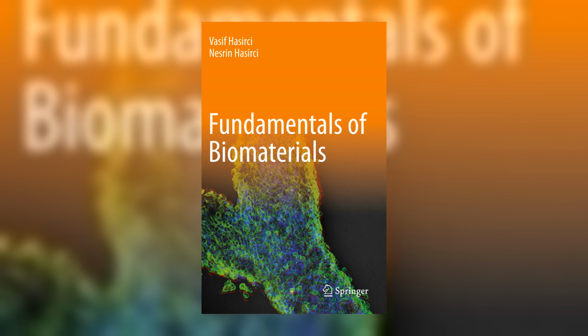This section explains ISO 10993, Part 18, the chemical characterization of materials. Before you ask the body how it reacts, ask the material what it is. Part 18 is the chemical arm of the biocompatibility series. Its task is to identify and quantify every constituent of a device and, critically, everything that can migrate out of it, the extractables and the leachables, before any biological assay runs.